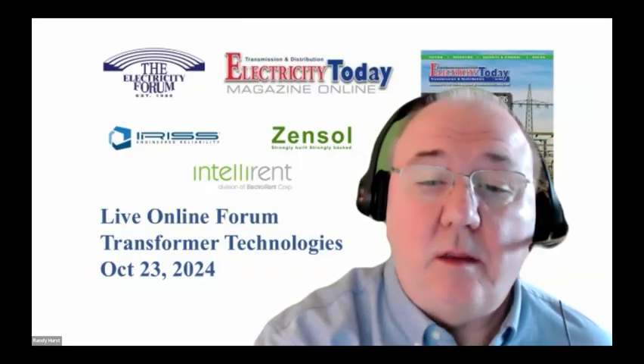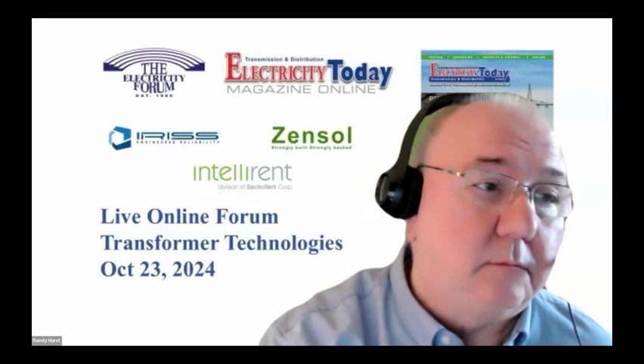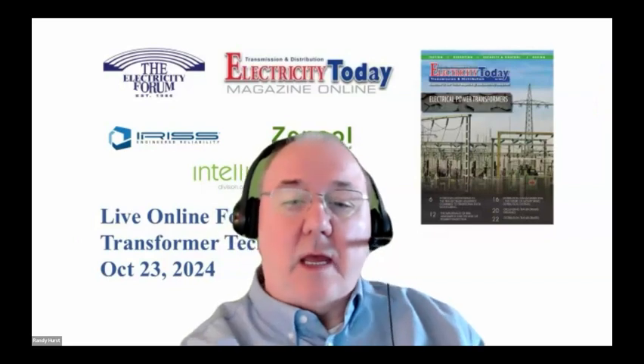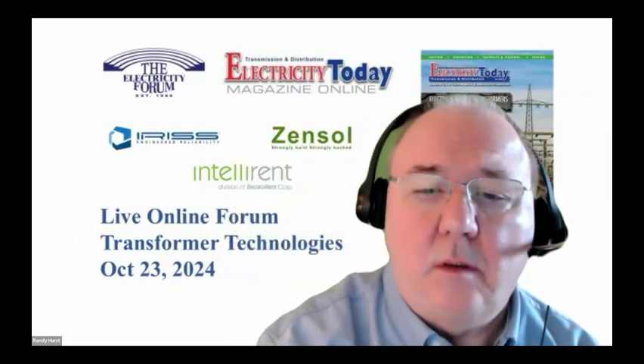So how safe is it to install on the bus bar? Is there a risk of fire? Yep, perfect. So as far as safe on bus bar, obviously you'd want to turn the power off before you apply this to a bus bar. And so, it'd be de-energized gear. Then you could apply this onto a bus bar safely, and obviously test before, even after you remove the power, test to make sure the power is off and then apply that safely. The risk of fire, these are not flammable, and there is no risk of fire when you put these on an asset.